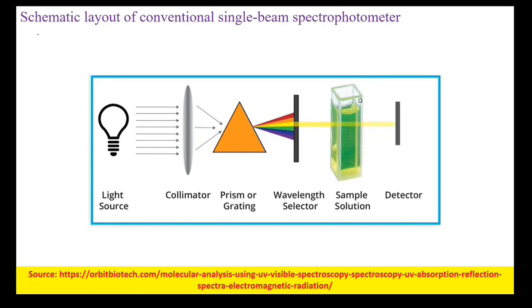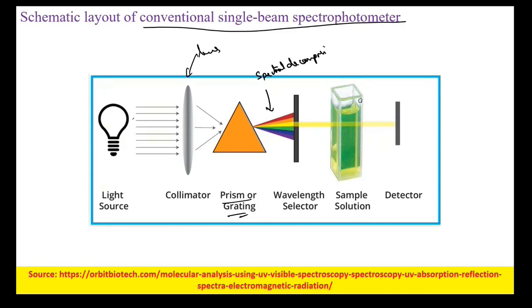The schematic layout of a conventional single-beam spectrophotometer has a light source; the radiation falls on a collimator lens which condenses the light over a prism or grating for spectral decomposition. After the spectral decomposition, there is a slit which acts as the wavelength selector. That specific wavelength of light passes through the sample and then reaches the detector. This is how a single-beam transmission spectrophotometer works.